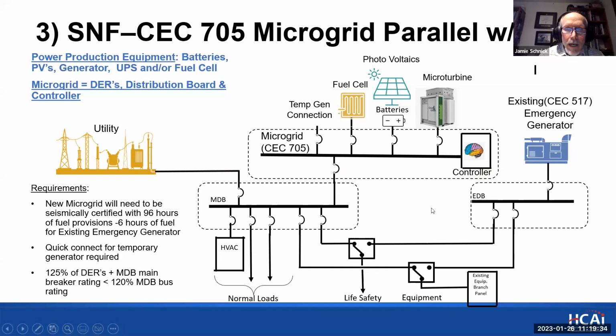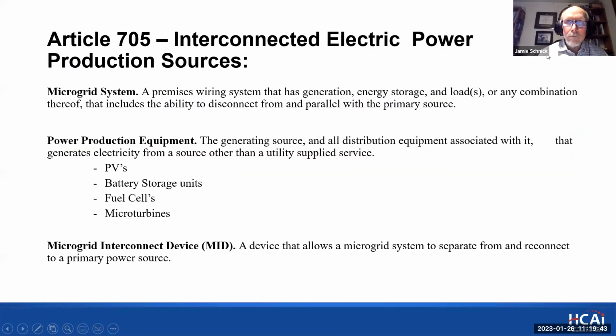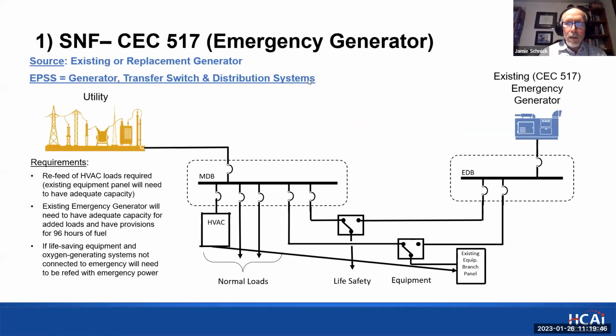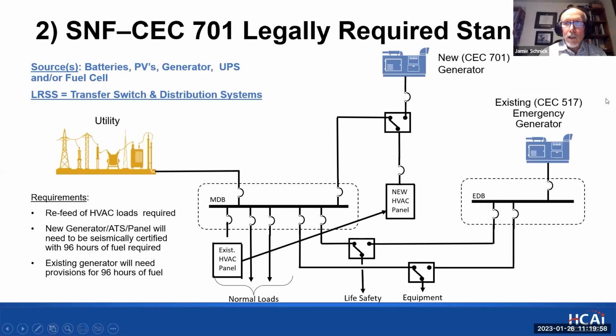Now, I want to revisit what I think is an important point. When we talk about 517, this is the emergency system, and the code drives requirements for the emergency system that need to be met. In this scenario, this is a standby system, and the code has requirements. You've got to follow NFPA 110 on the generator, but it's not the emergency system. It's a separate branch from emergency. So all the requirements from 517 necessarily don't apply to this.